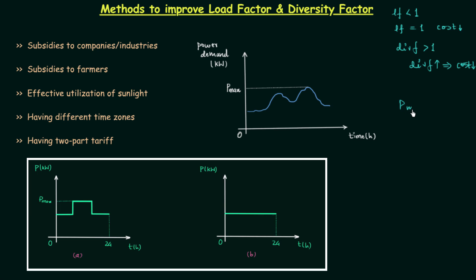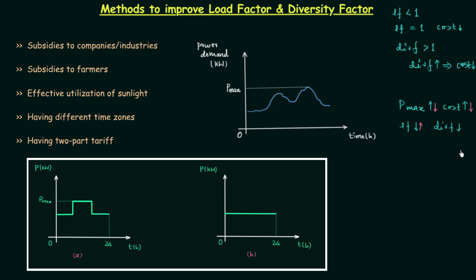When P_max — the maximum power demand — is higher, that is the peak load condition, the cost of electrical energy increases. And when P_max is higher, the load factor, which equals average power demand over maximum power demand, reduces. Diversity factor also reduces. If we think in the reverse manner, if we can increase the load factor then P_max will reduce and the cost of electrical energy will also reduce. The same applies to the diversity factor.